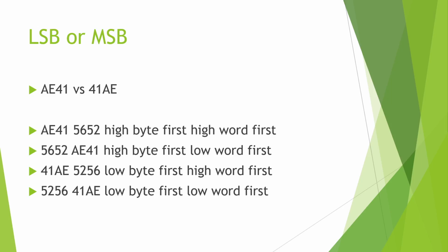All right, but could you imagine that screwing up your coding in your PLC? You're thinking you're getting 0, 0, 1, 1, 0, 1, 0, 0, and in fact they're sending 1, 0, 1, 0, 1, 1, 0, 0. And you're looking at when this sensor goes true in the real world. There's a part in front of that sensor, so why is the PLC thinking there's not a part in front of that sensor? And then you realize, oh, it's because this one is over here, not over there.